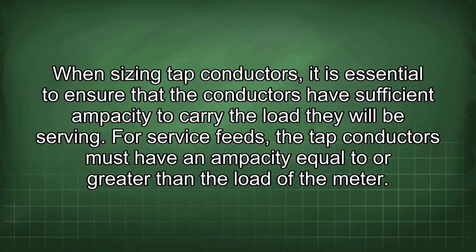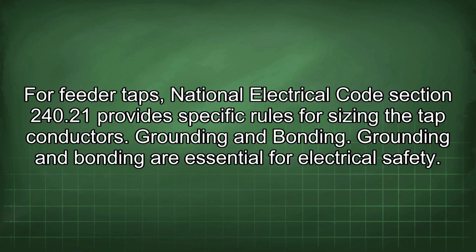When sizing tap conductors, it is essential to ensure that the conductors have sufficient ampacity to carry the load they will be serving. For service feeds, the tap conductors must have an ampacity equal to or greater than the load of the meter. For feeder taps, National Electrical Code Section 240.21 provides specific rules for sizing the tap conductors.